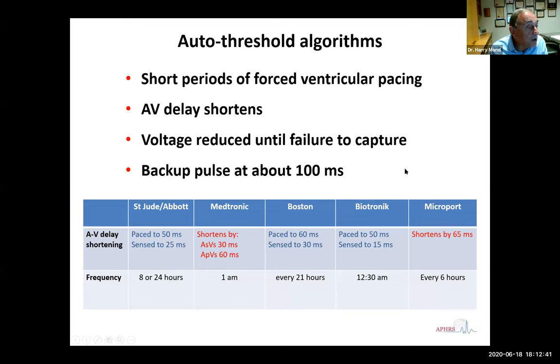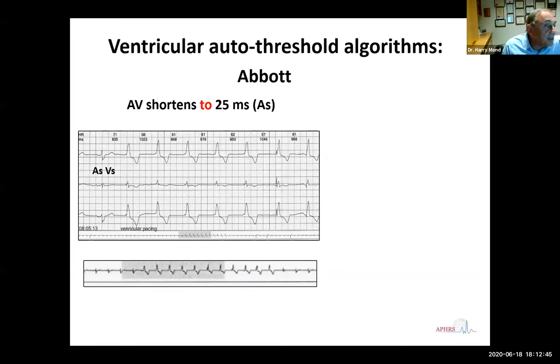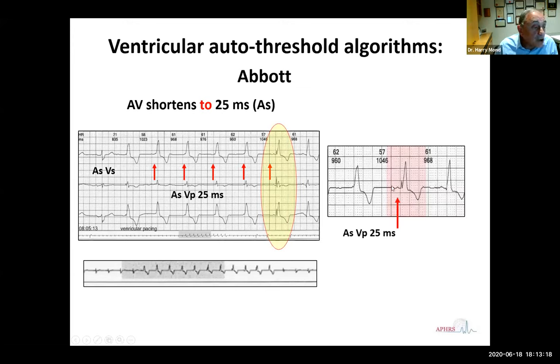Let us have a look at one, the Abbott ventricular auto threshold algorithm, where the AV delay is shortened to 25 milliseconds. You can see on this ECG there is atrial sensing and ventricular sensing almost all the time, and suddenly there's a short run of ventricular pacing, with atrial sensing before it, with only 25 milliseconds in the AV delay. If one looks at the last one and highlights it, you can see there is a longer AV delay here because there is failure to capture, and then at about 100 milliseconds later, a higher voltage spike emerges, and this is the termination of the algorithm. The threshold has been determined, and the pacemaker then adjusts the voltage output.